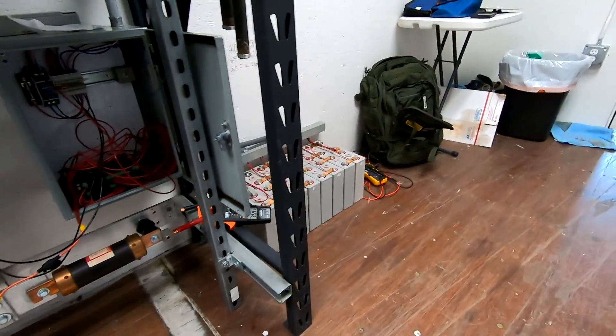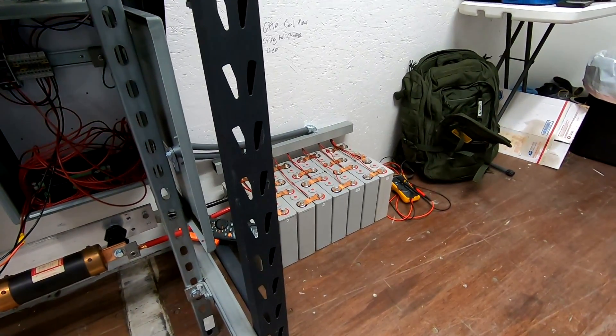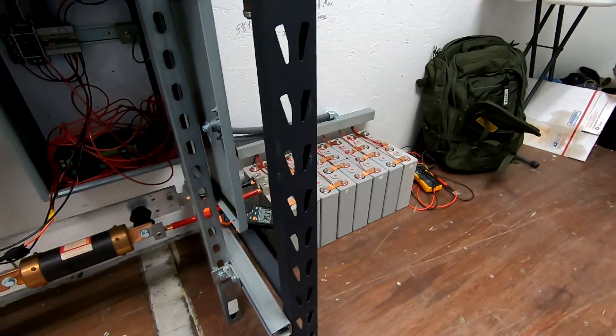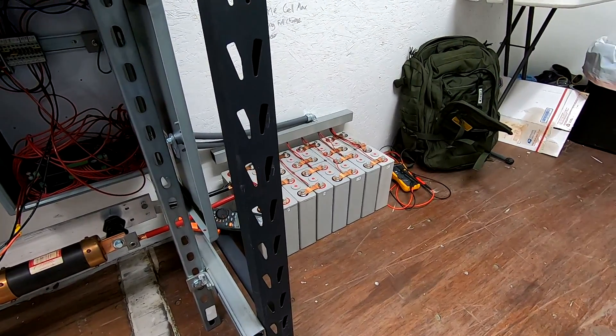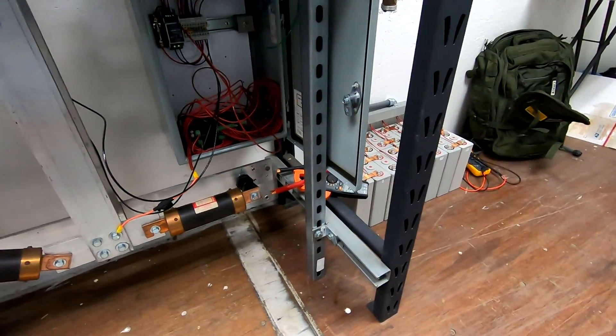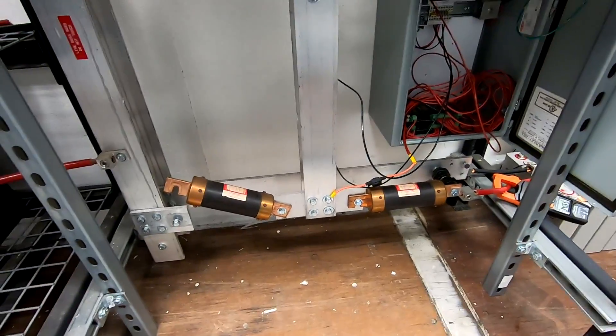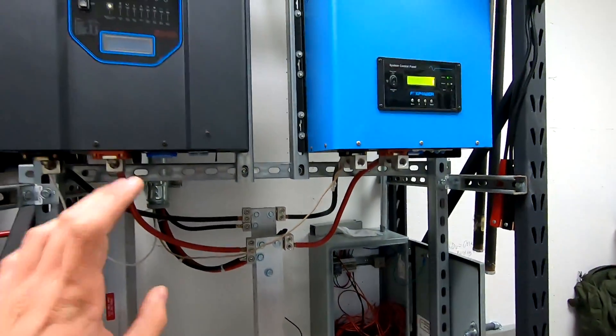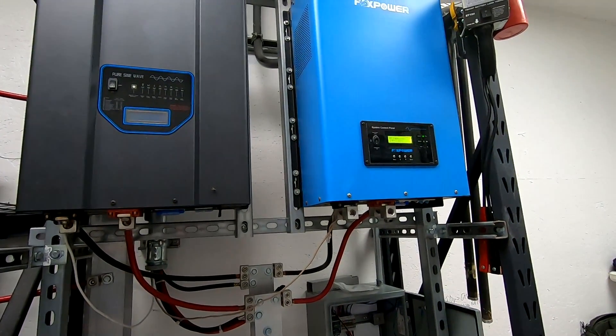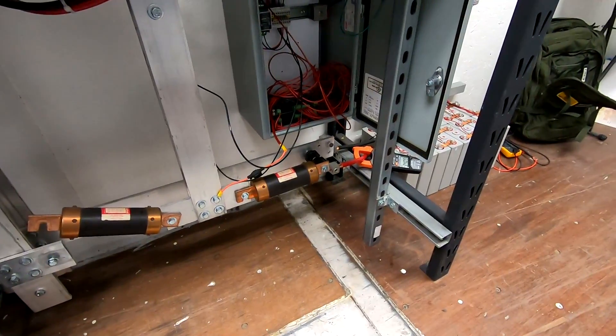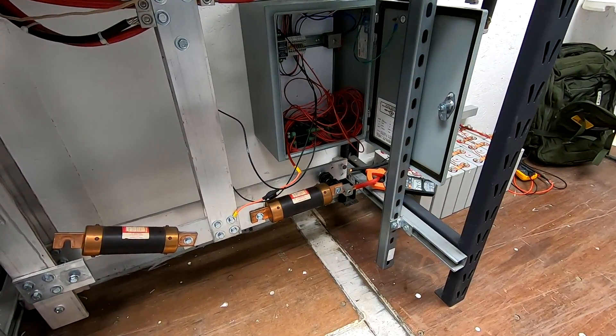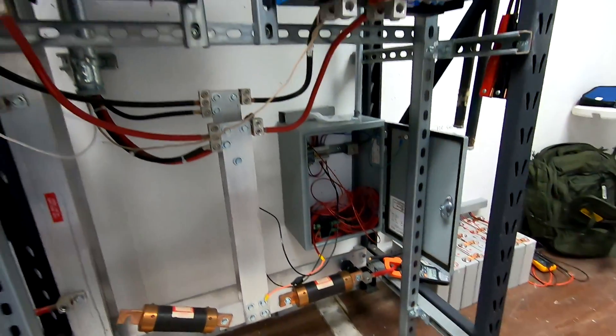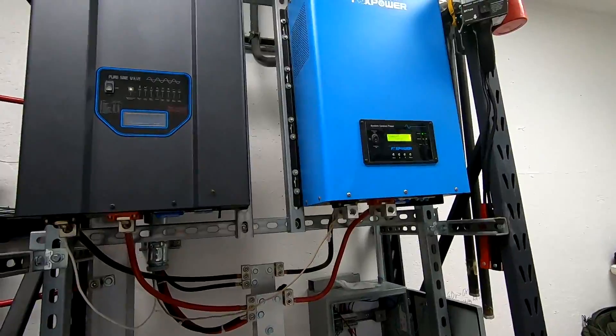And even though these cells are really small, I've had to start up the air compressor yesterday on these cells, and I had my meter set on min-max mode, and I was able to easily surge a 300 amp startup on that five horsepower compressor motor, and they didn't care one bit. One of the concerns is, if you just have these inverters off, and the internal capacitors discharge, when you first connect that battery terminal, and the inverters are trying to charge up, there's such a huge inrush available that it can actually blow apart the traces on the circuit board.